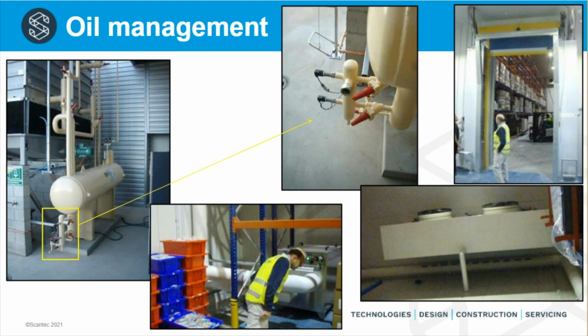This is a very, very high usage cold store. There's a very large door that is open to an area that is held at about 5 degrees C, and that large opening is used for picking of product for approximately 15 to 20 minutes per hour. It's very important to minimize infiltration here.